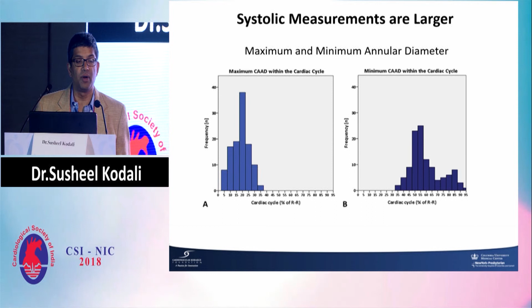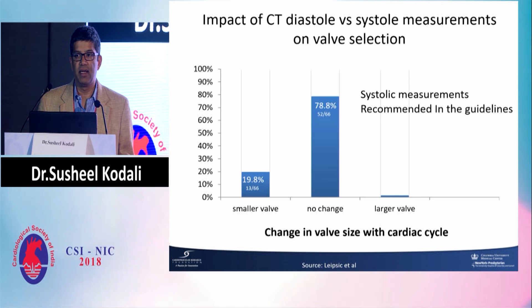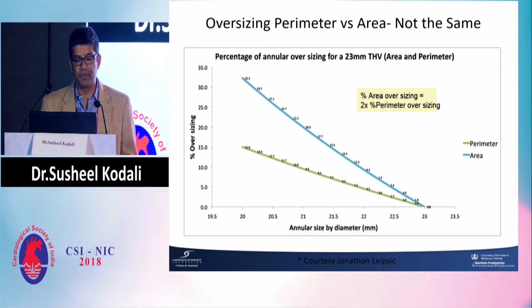And this is from Jonathon Leipsic, the same group in Vancouver: in 20% of patients, if you use diastolic measurements instead of systolic, you choose a smaller size in this analysis. That's dramatic because you have to size appropriately. If in 20% the valve size would be off by using diastole rather than systole, that's an important consideration. Perimeter and area are not the same. Area is roughly 2 times perimeter sizing. And these are all relevant. There are multiple analyses showing three-dimensional measurements can predict PV leak, so you can't do a simple 2D measurement anymore, and you have to do these 3D measurements.